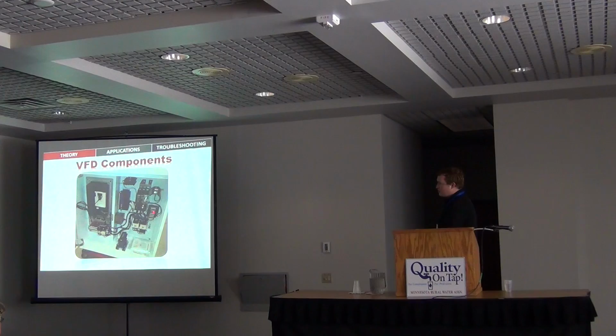Over here on the right is a control power transformer. It steps your 480 volt down to 120 for the controls. From here, it looks like it runs over to this VFD. This is the VFD itself. This is the device that has all the brains, and when we have problems, that little display on the front might give you an error code.